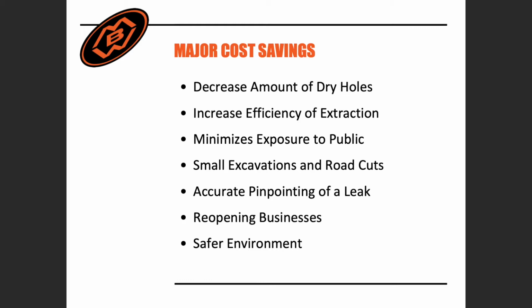When running a series of probes off the VEU over time, the LEL levels of gas in each bar hole will decrease. The bar hole that stays consistent or is hot and is not zeroed out is where your leak is. The efficiency of using the VEU will expedite the extraction process tremendously. You are able to deploy up to 18 probes and cover a wider range of gas migration with one machine.